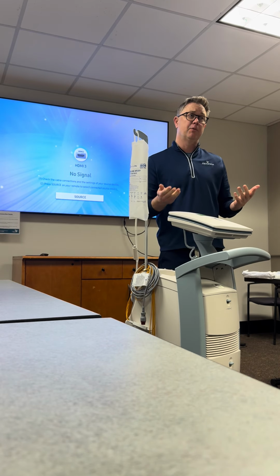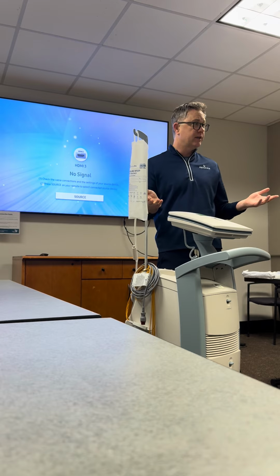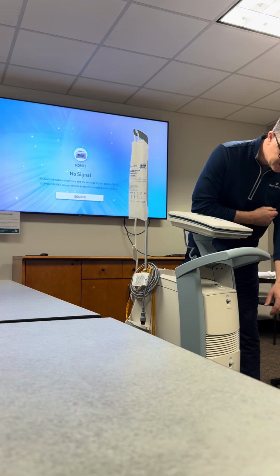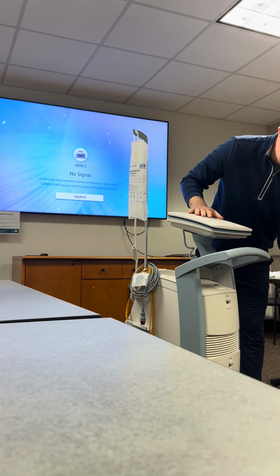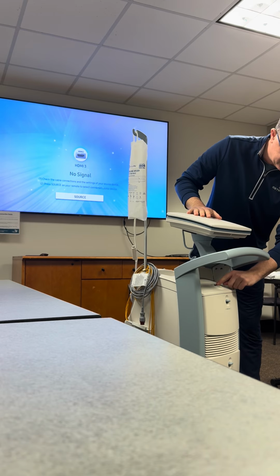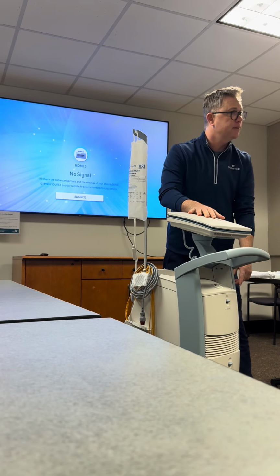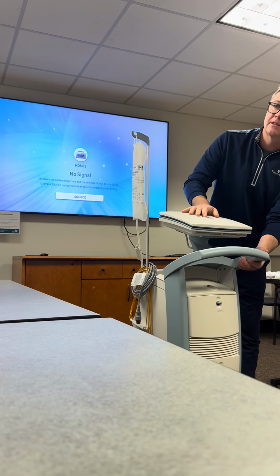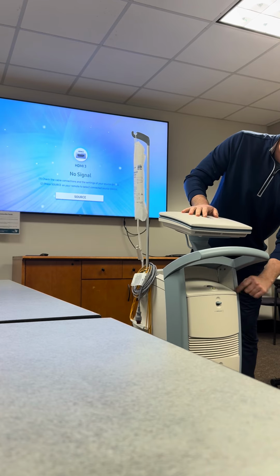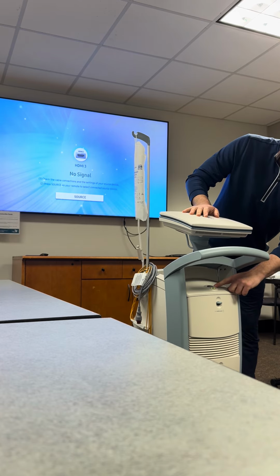Typically these will last a couple years, especially at a lower volume center like you guys. So when you're going to grab a balloon pump, if you just want to do a quick check and see how much helium you have, there's an external gauge right here. Looks like there's about a quarter of a tank left. So that's where your helium gauge is.